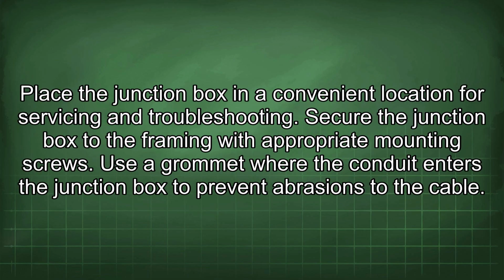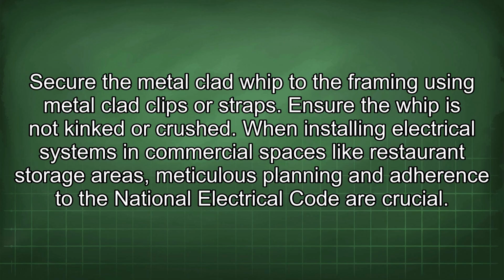Place the junction box in a convenient location for servicing and troubleshooting. Secure the junction box to the framing with appropriate mounting screws. Use a grommet where the conduit enters the junction box to prevent abrasions to the cable. Secure the metal-clad whip to the framing using metal-clad clips or straps. Ensure the whip is not kinked or crushed.